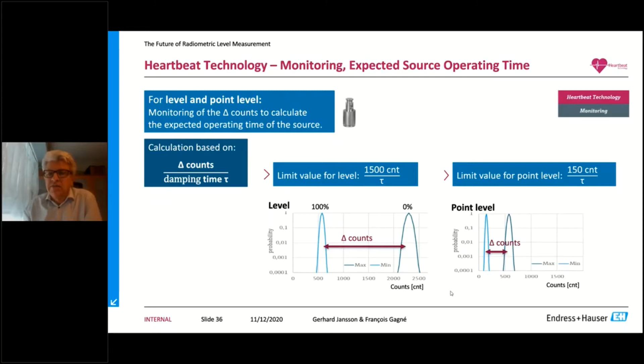As time goes by, this difference is going to decrease. And what you are going to start to lose is the ability to measure down at the bottom of the vessel. So that is going to happen eventually, and it's a matter of how long. This will give us an idea of how well the instrument performs. On the level switch, we have something else, but the difference is smaller, and it might be that you just need to adjust that again, and it would still probably work well.